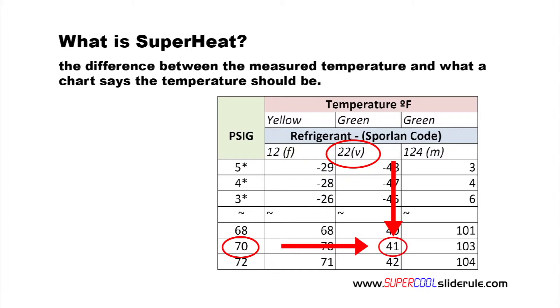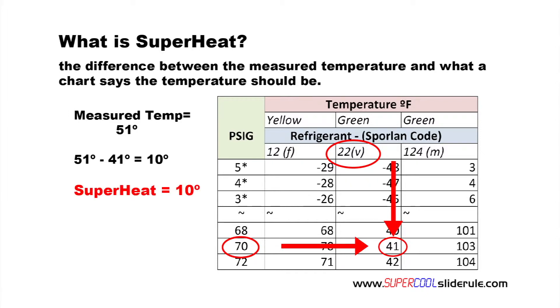If we measure the temperature of the refrigeration suction line and it is actually 51 degrees, this is 10 degrees warmer than it should be, so our superheat is 10 degrees.